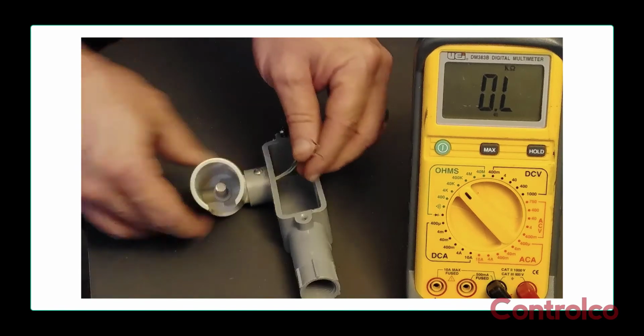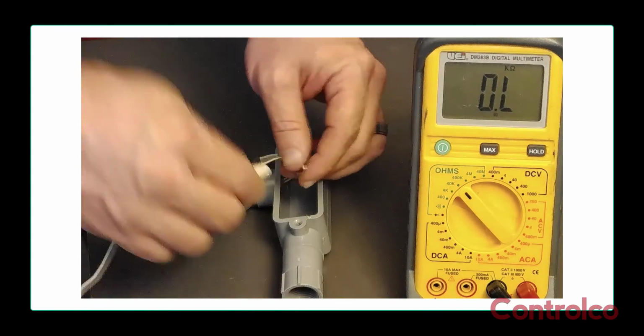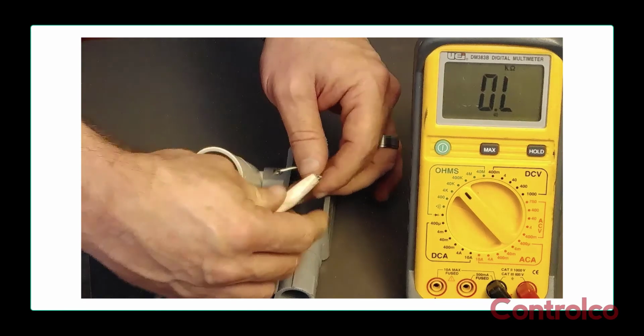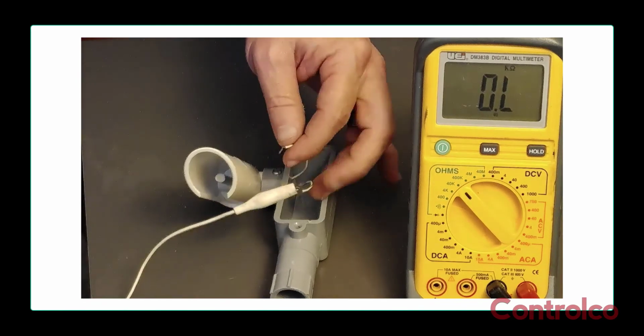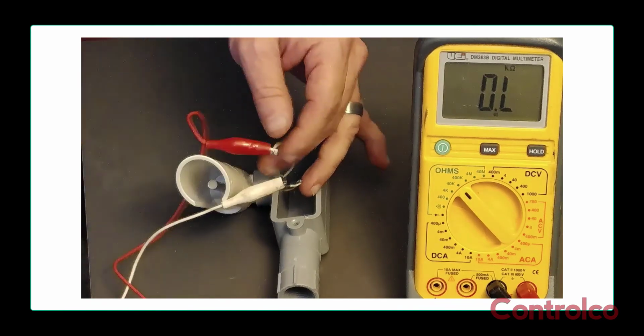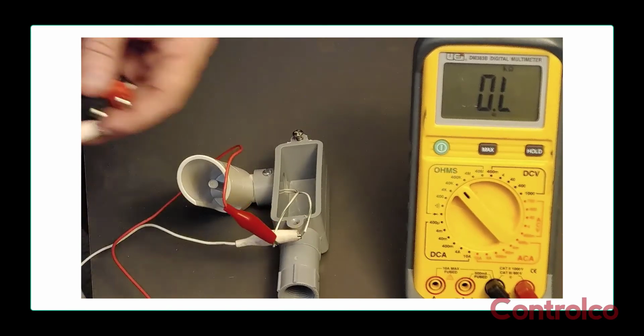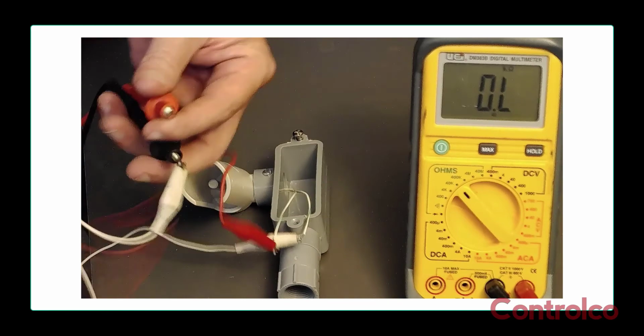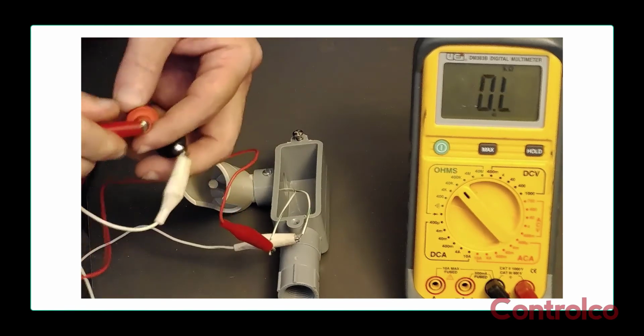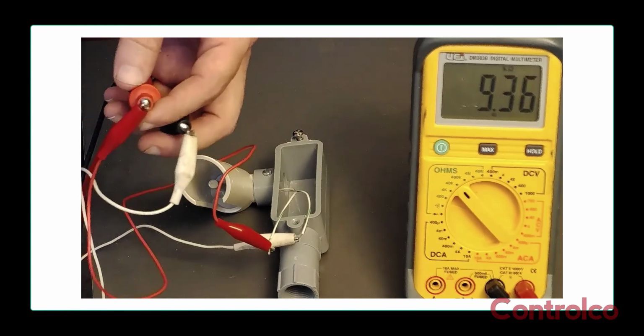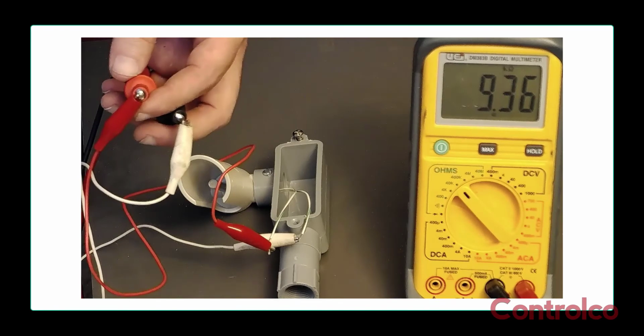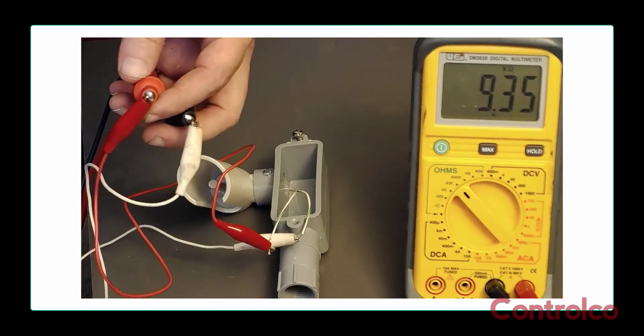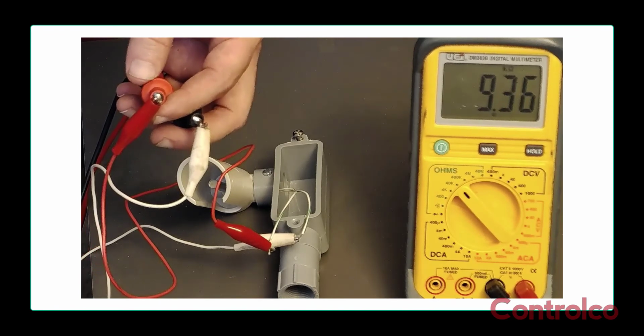I'm going to go ahead and hook my meter up, and I'm just using jumper cables because I don't want to stand there and hold the probes. And you can see that my meter starts reading right away. I have the meter set on 40,000 ohms for my resistance scale, and I'm picking up 9,360 ohms. So 9.36 on a 40,000 scale.